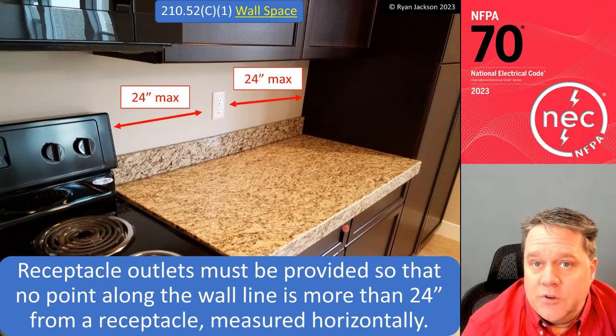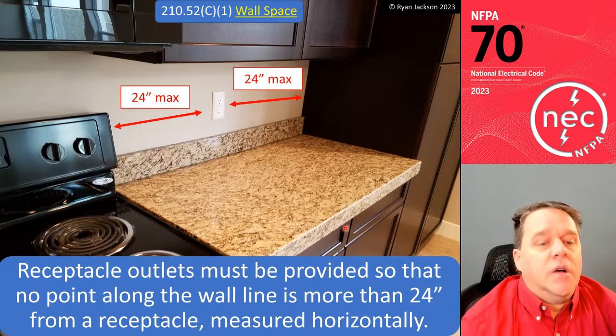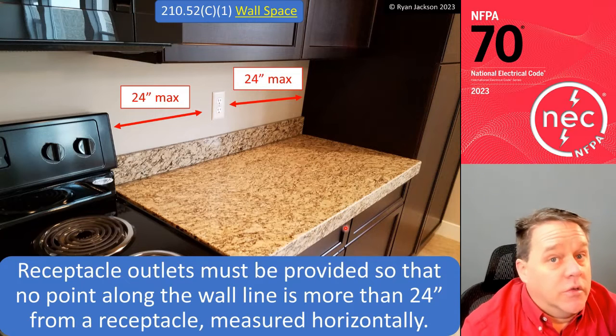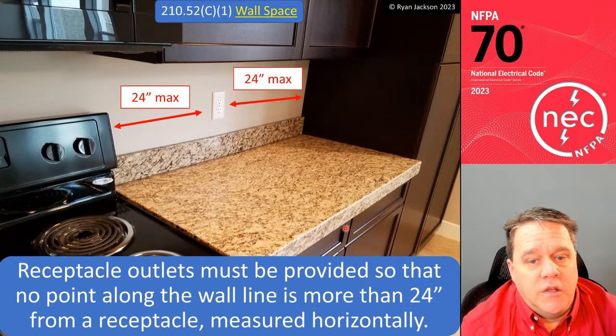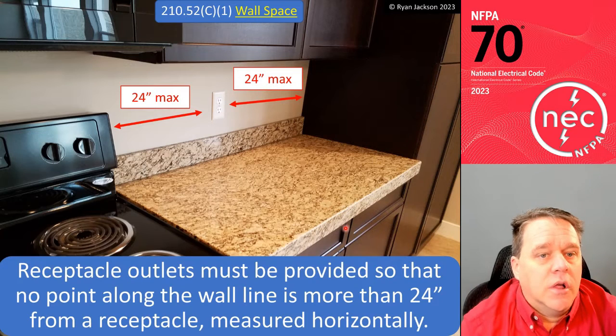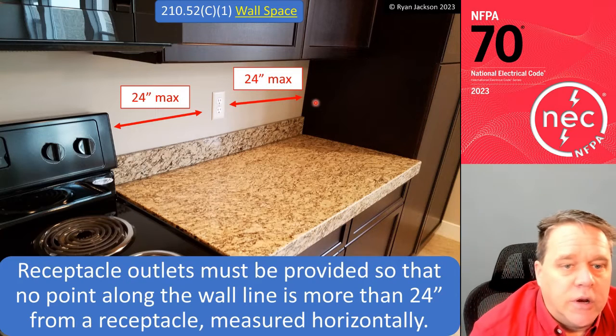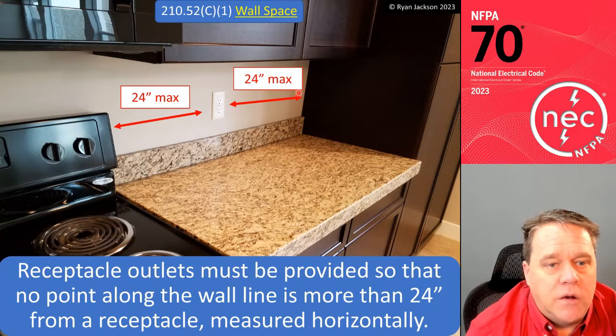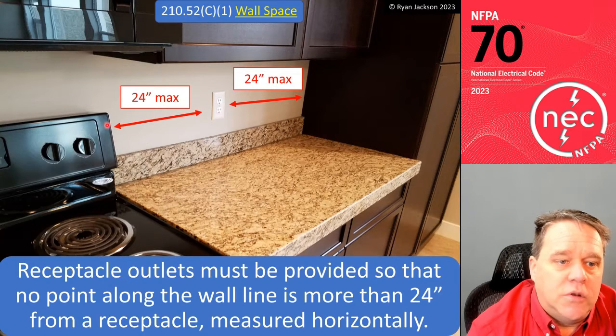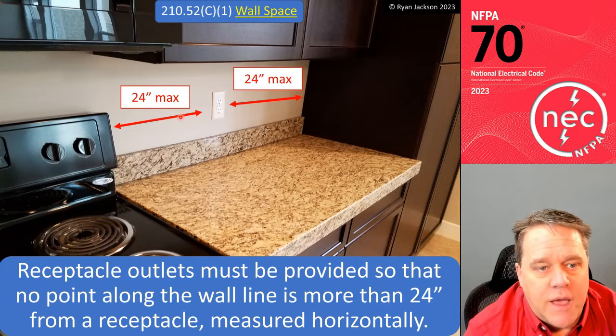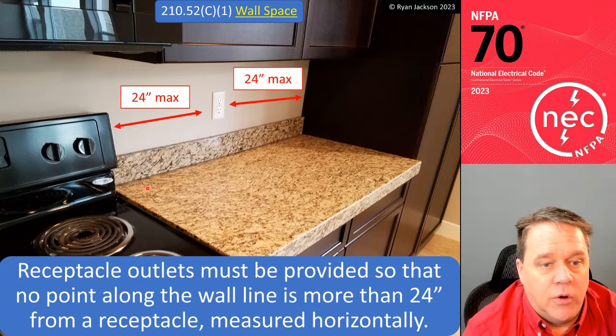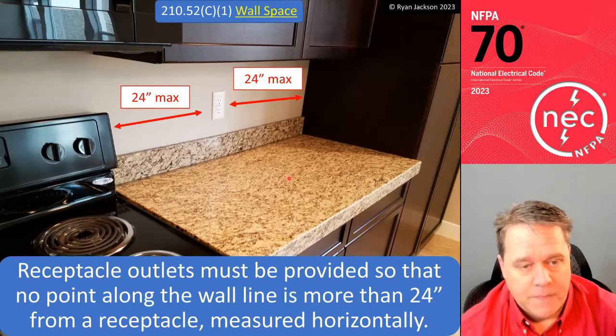All right, wall space. Where do you need these receptacles? Receptacle outlets must be provided so that no point along the wall line is more than 24 inches from a receptacle measured horizontally. We're going to butt our tape into the cabinet here on the right, pull it to the left, need a receptacle within 2 feet. Butt our tape into the oven here, pull it to the right, need a receptacle within 2 feet. So if this total is less than 4 feet in width, then you only need one, right?